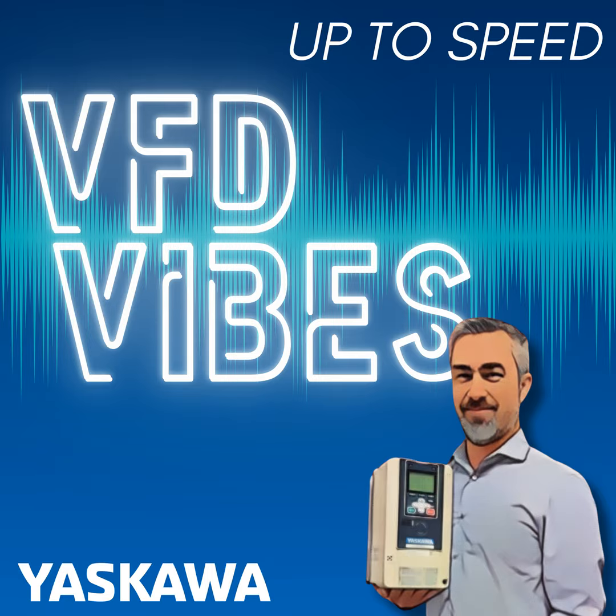Well, it was my job as a tech support engineer to convince you that the problem was outside the drive, which is 99.9% of the time the case. And I did that by confirming a run command and speed reference. And oftentimes I'd have the customer say, yeah, we're sending a run command on S1. We have 10 volts on A1. And they were telling me exactly what questions I was going to ask. So I kind of knew maybe they were a little above average as far as abilities with the drive.